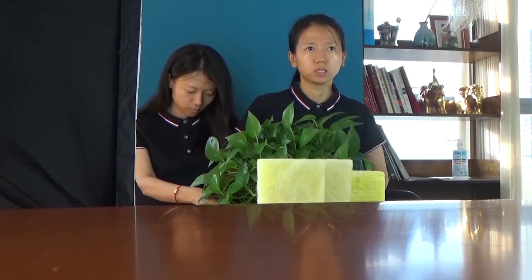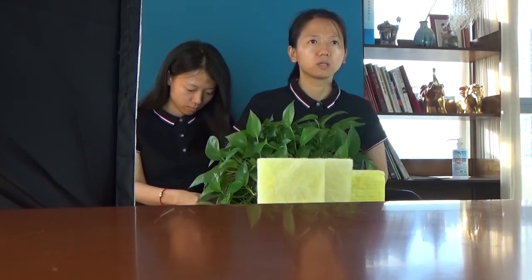And for the ceramic fiber blanket, the widely used densities are 96 kg per cubic meter and 128 kg per cubic meter, with thickness like 25 millimeters and 50 millimeters. The ceramic fiber blanket is normally used in industrial fields like power plants, boilers, furnaces, and so on.